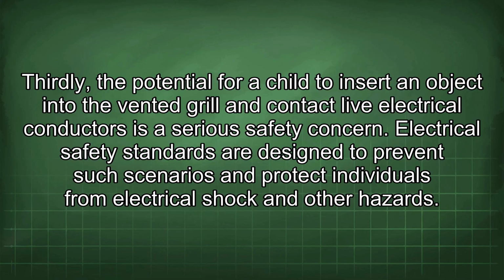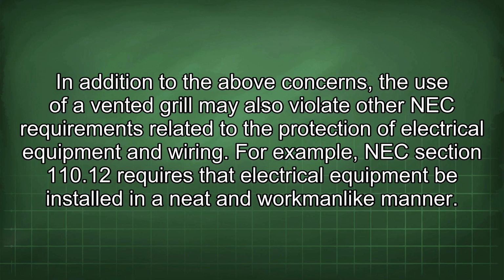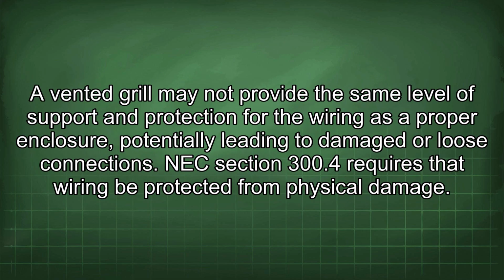other hazards. In addition to the above concerns, the use of a vented grille may also violate other NEC requirements related to the protection of electrical equipment and wiring. For example, NEC Section 110.12 requires that electrical equipment be installed in a neat and workmanlike manner. A vented grille may not provide the same level of support and protection for the wiring as a proper enclosure, potentially leading to damaged or loose connections.